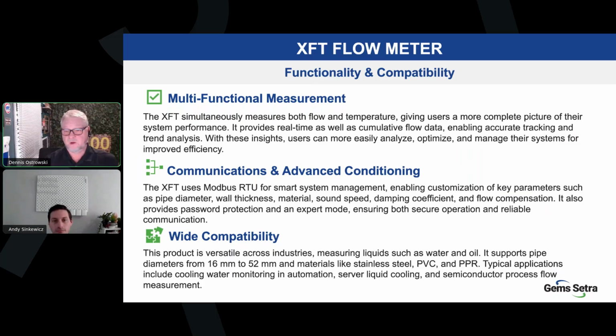Okay. The functionality, okay, it has multifunctional measurement. It simultaneously measures both flow and temperature, provides real-time flow data and temperature data, as well as cumulative flow data. It does this, the real-time, via a 4 to 20 milliamp output that gives you real-time flow rate and pipe wall temperature. The cumulative data, you can program the device so that could be on the display, and that data can also be transmitted via Modbus.